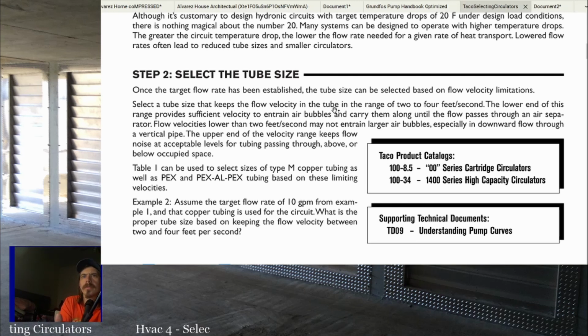The lower end of this range provides sufficient velocity to entrain air bubbles and carry them along until the flow passes through an air separator. Flow velocities lower than 2 feet per second may not entrain larger air bubbles, especially in downward flow through a vertical pipe. The upper end of the velocity range keeps flow noise at acceptable levels for tube passing through, above, or below occupied space.